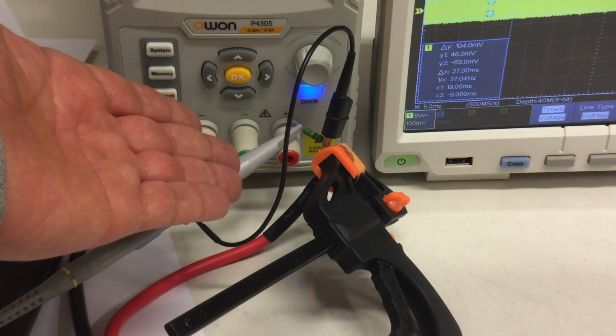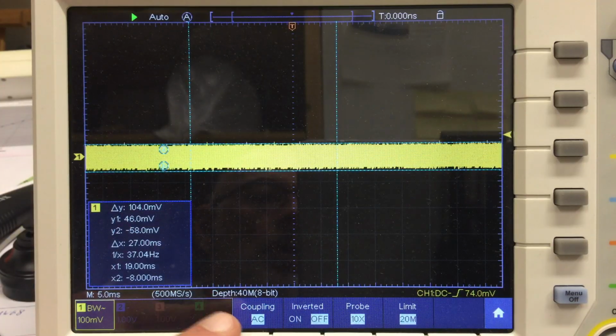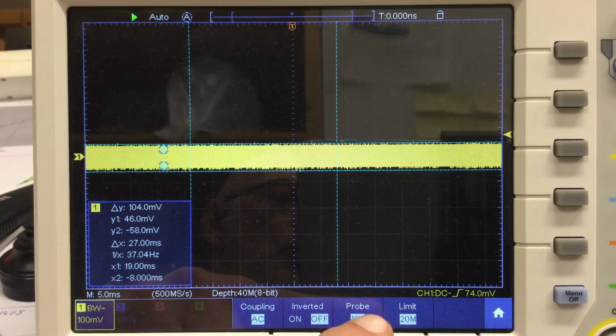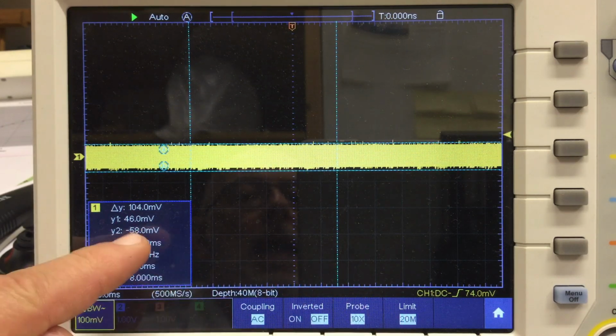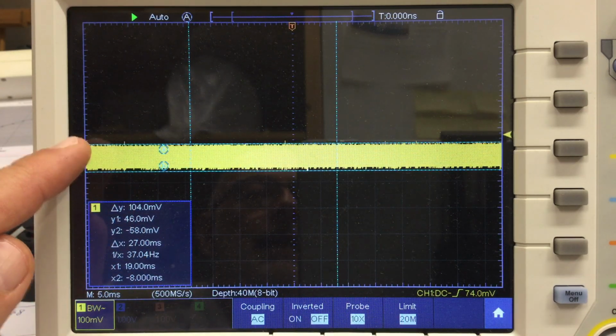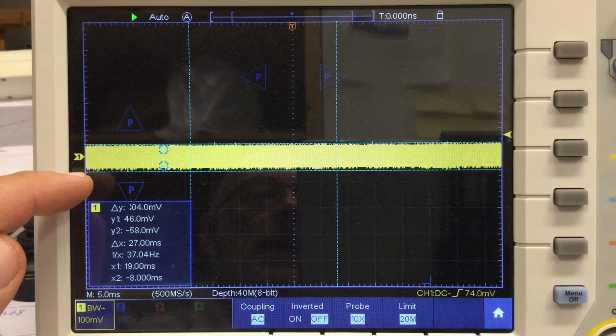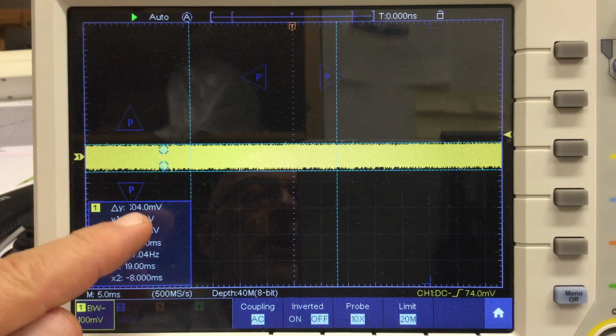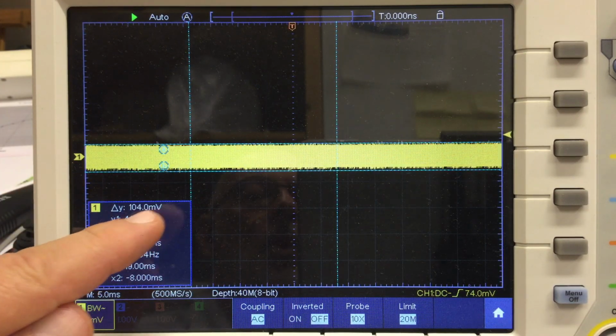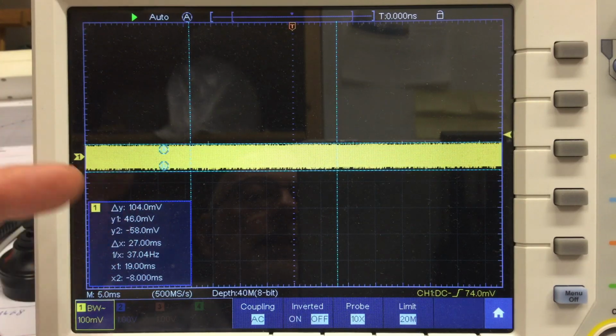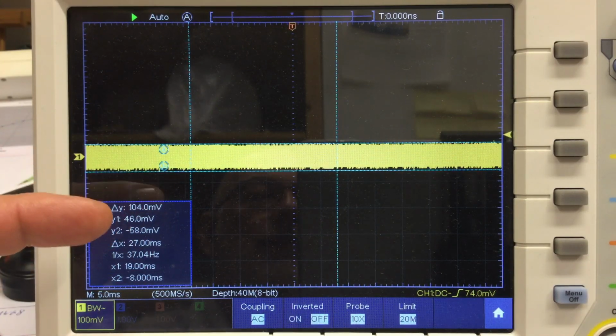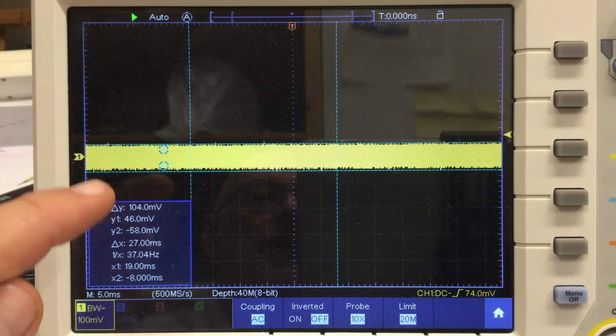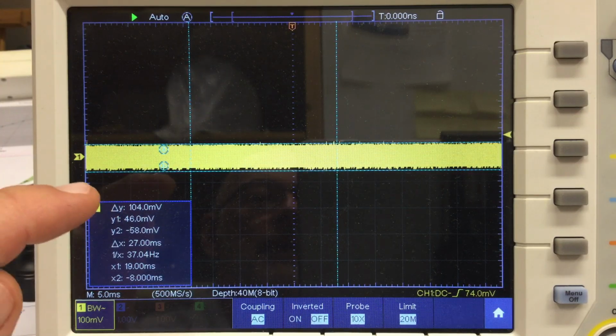Let's do some measurements now. I have the probe AC coupled with the bandwidth limit at 20 megahertz. Already, without the motor even running, we are measuring a noise level of about 100 millivolts. That's quite a lot, but we do have quite long battery cables connected to the whole thing.